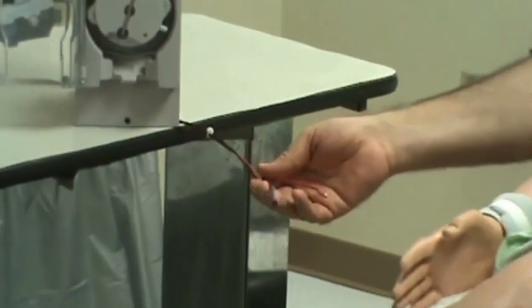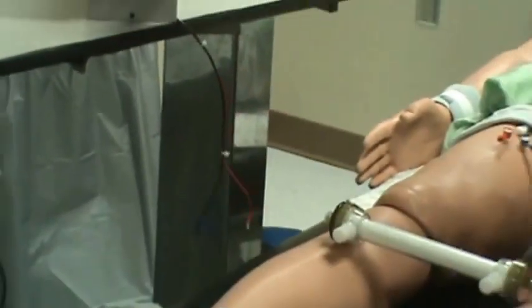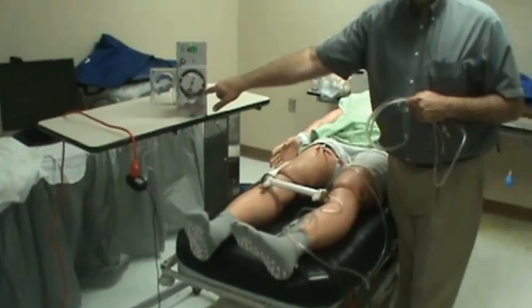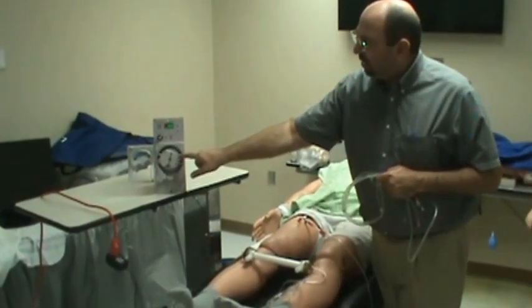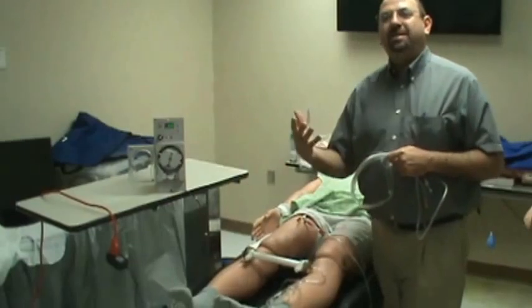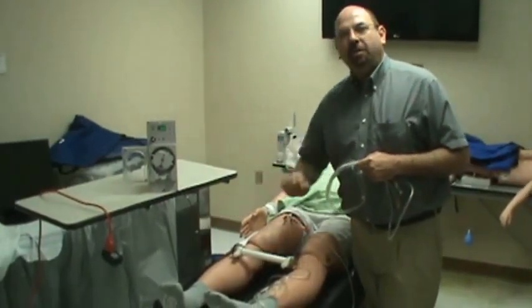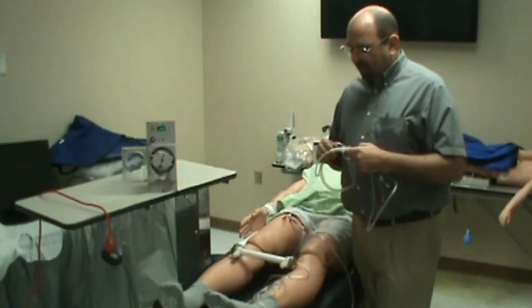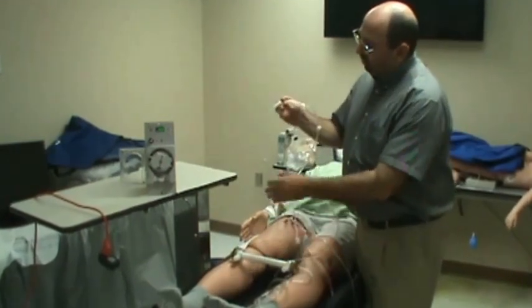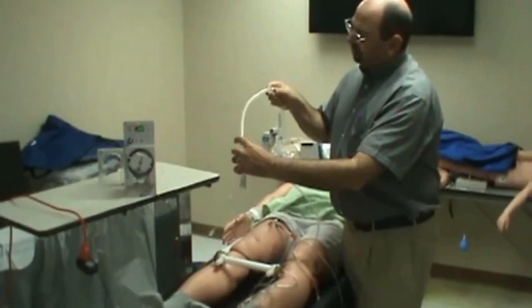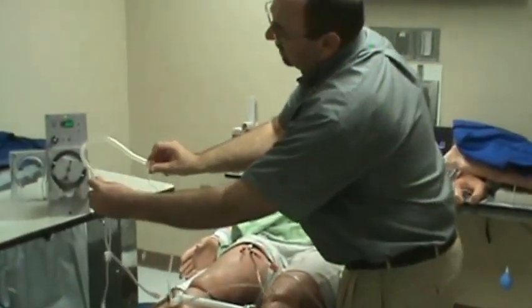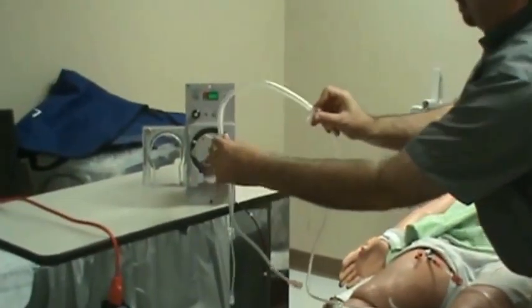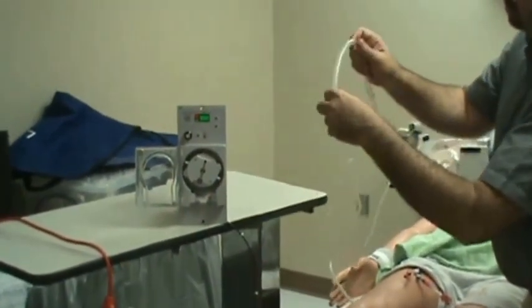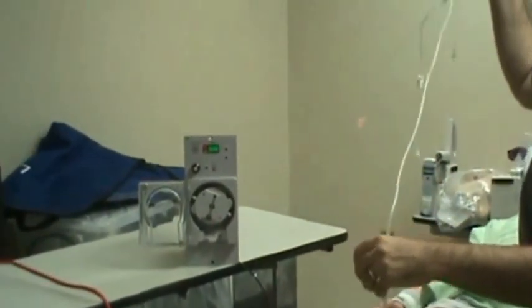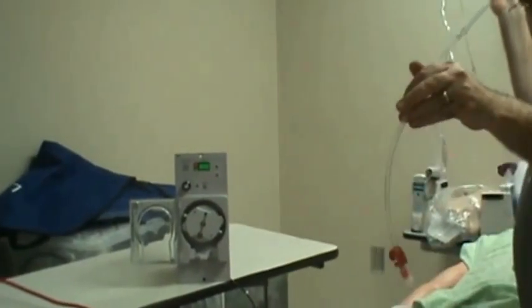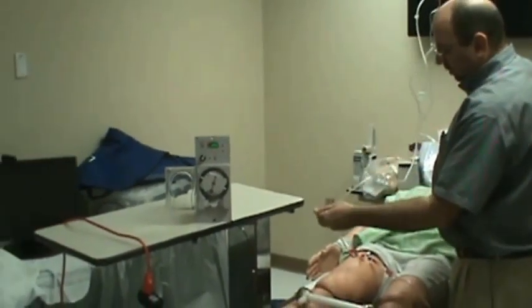Now, if you are doing this, keep in mind the pump has to be rotating clockwise. If it's rotating counterclockwise, what you have to do from a technical electrical standpoint is reverse the connections. Now, the tubing has what we call a pump segment, which is the segment that's going to be sitting inside the pump. Now, the proximal element of that tubing has to be the patient end. This is the patient end that connects here.